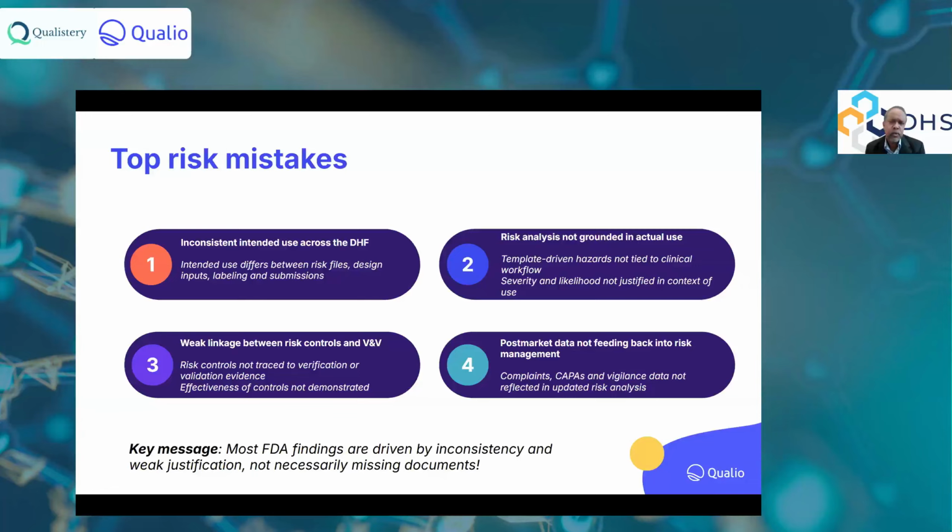For example, if you have a tool that does some blood analysis and tells a physician about some biomarker measurement, but the tool is strategically placed as one of the tools a physician uses, along with their clinical training and other data, to make a decision, the hazards and the severity associated with hazards are much lower in nature. You cannot be misaligned with regulatory strategy. That would be a disconnect, like I talked about earlier, and not result in good outcomes. So that's the second category.